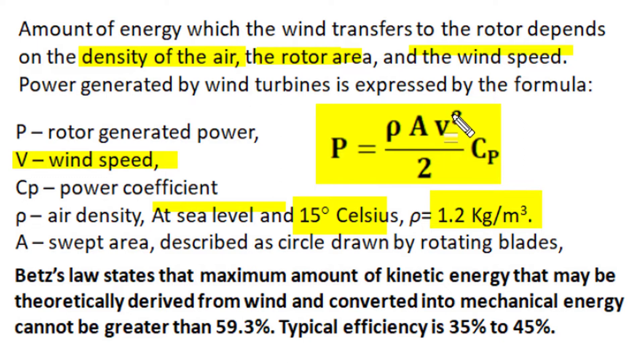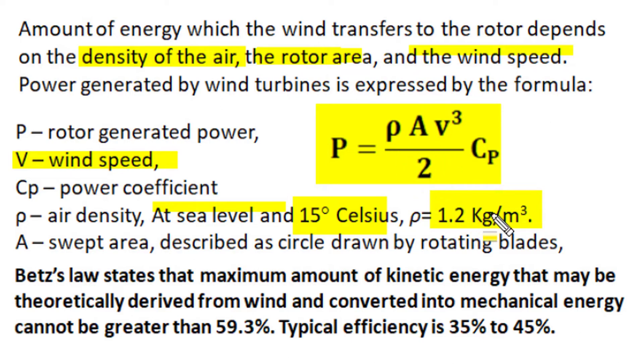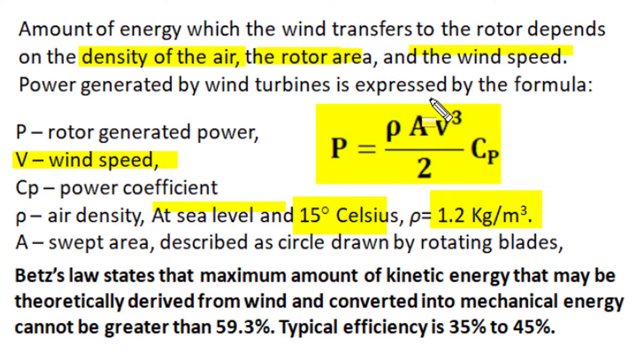Power output is proportional to the cubic power of wind velocity, meaning if wind velocity increases by 1%, the power output may increase by 3%. A is the sweep area — the circle drawn by the rotating blades. Cp is the power coefficient, which represents the utilization of wind kinetic energy to produce mechanical power at the rotor. The Betz limit states that the maximum fraction of kinetic energy of air that can theoretically be converted into mechanical output from a wind turbine cannot be greater than 59.3%.